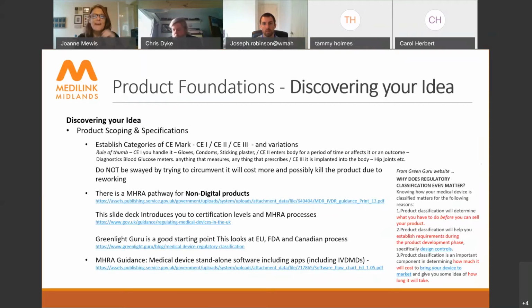Yes, Chris, I was going to say it really is important to explore what CE mark you will be, or think you will be, as early as you can in the process, and then keep reassessing as you go forward. We recently had a company that came to us through the WMAHSN network. They had a monitoring and alerting system for use in hospitals for various different clinical cohorts, but they had it as a CE Mark 1 product. Now, the problem there was because it actually does alert, so it alerts the staff that something might be wrong, that is not a CE1, it has to be CE Class 2A.